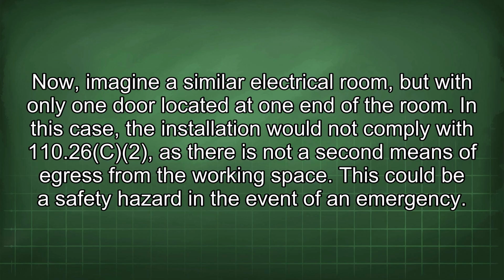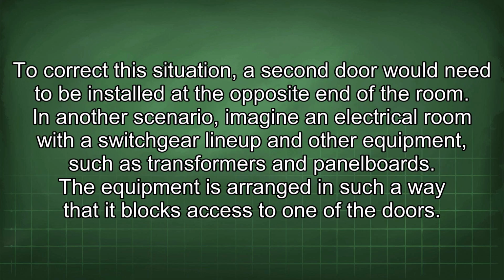Now imagine a similar electrical room, but with only 1 door located at one end of the room. In this case, the installation would not comply with 110.26(C)(2) as there is not a second means of egress from the working space. This could be a safety hazard in the event of an emergency. To correct this situation, a second door would need to be installed at the opposite end of the room.